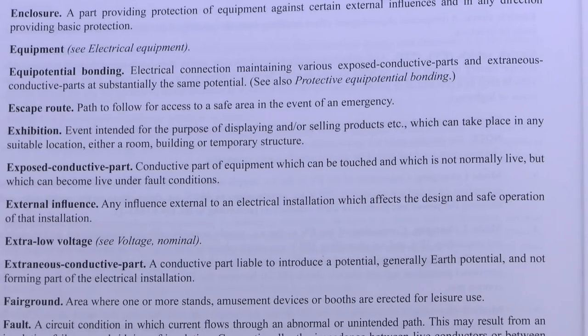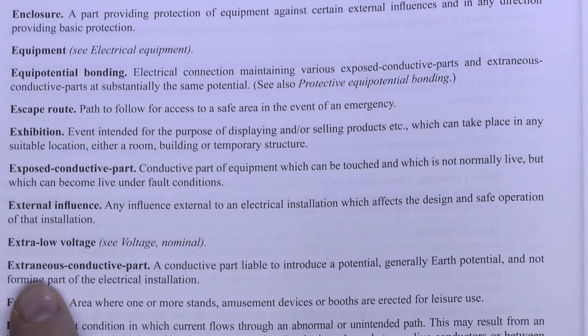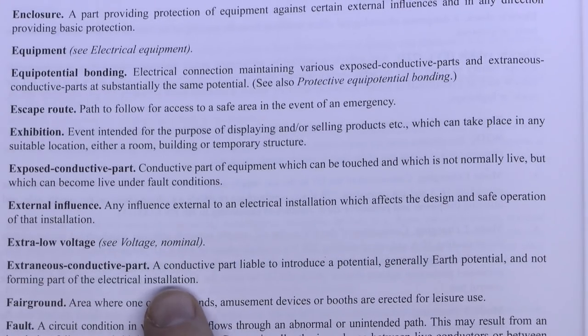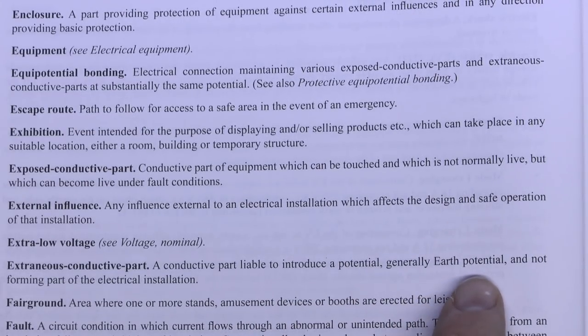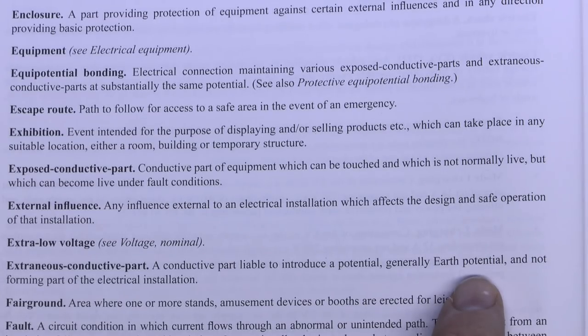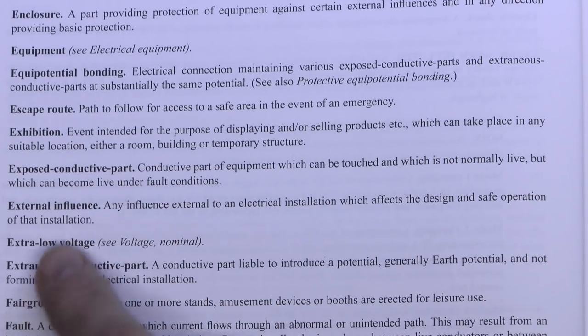Exposed conductive parts are not normally live but can become live if there's a fault, such as shorting onto the metal case of a socket. The other definition is extraneous conductive parts — still conductive and still a part, but in this case extraneous. This is a conductive part liable to introduce a potential, generally earth potential, and not forming part of the electrical installation. This covers conductive items typically made of metal and not part of the electrical installation.